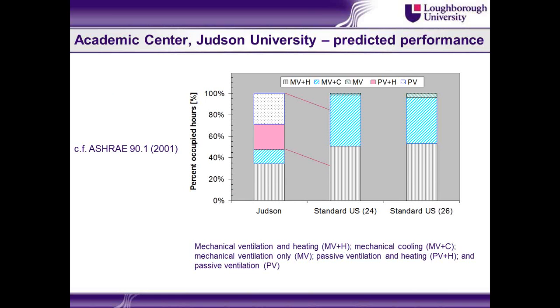The predicted performance then, so just comparing with ASHRAE benchmarks here for two different set points, 24 degrees C and 26 degrees C. So in this benchmark, we've got the mechanical ventilation heating here, and then we've got the mechanical ventilation and cooling here. The object of this design was to put a dent in those two chunks of energy use by applying passive ventilation and heating, which is this pink one here, in the winter time, and passive ventilation cooling, sorry, without any mechanical cooling in the summertime. And the dynamic thermal simulations we undertook predicted that we could displace about 50% of this mechanical energy with the passive measures.